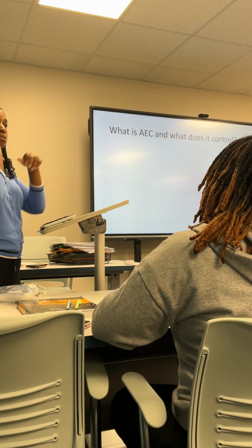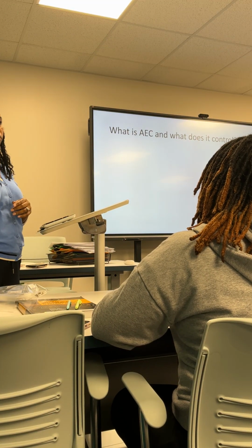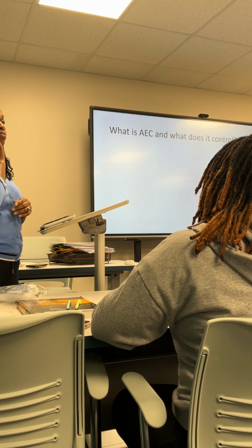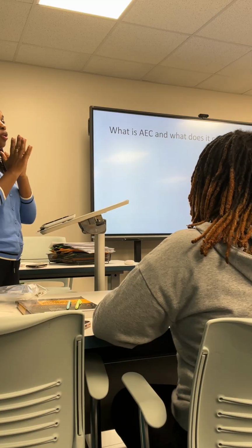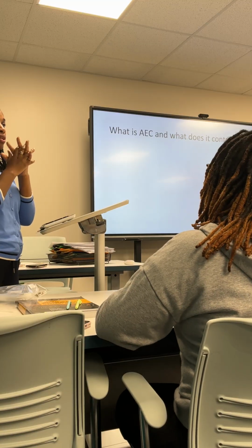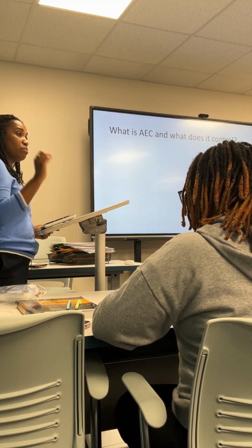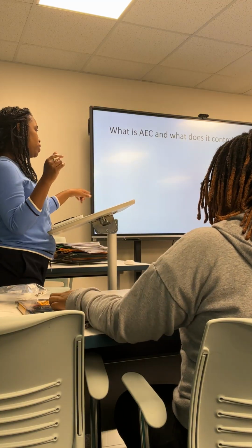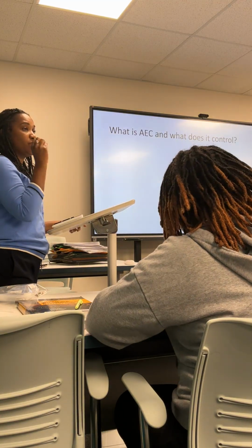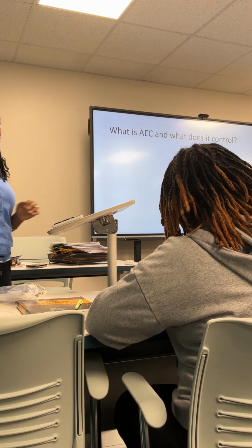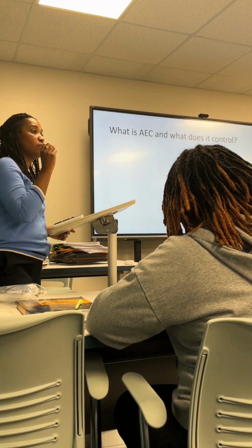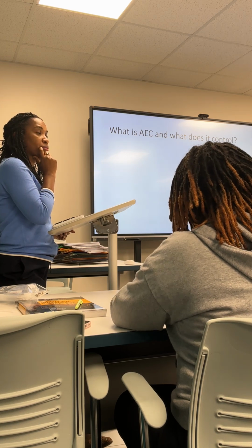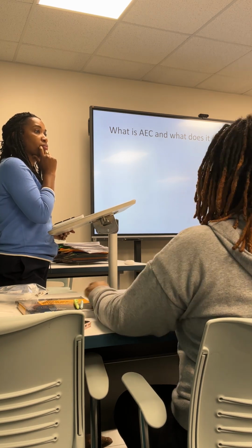Okay. Emily? And you said that the anode has two filaments? The cathode. So remember, filament is only associated with the cathode. And there's two little filament springs. Don't let me forget to show y'all the tube because it has the filaments. Okay, so I can show y'all what it is. Just two springs. Like with a light bulb, you can turn on one, and then you switch it, it'll go brighter. Those are like the two settings.